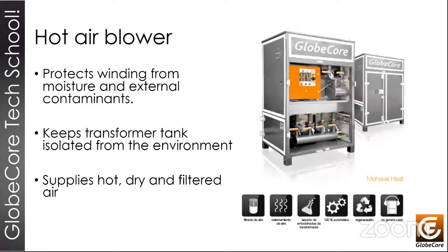This is a hot air unit. It's a piece of equipment that allows generation and output of hot, dry air. So when oil is removed from a transformer for repairs, obviously the transformer core should be isolated from ambient humidity, because that can be very harmful. This hot air unit generates a very dry airstream, and it keeps moisture out of the transformer. And the recommended dew point for this purpose is about -70 degrees centigrade.